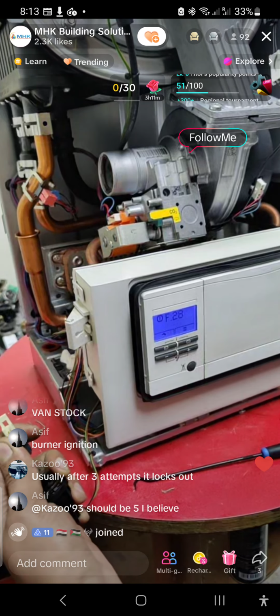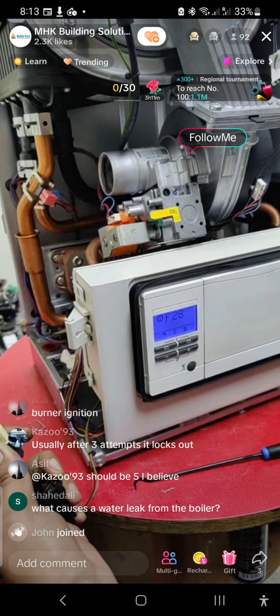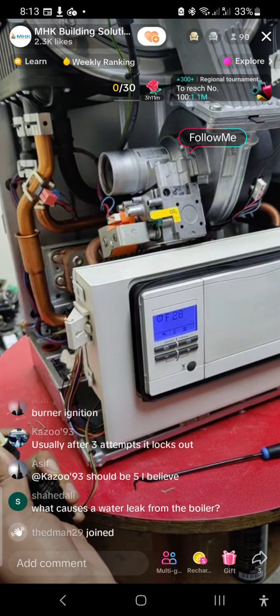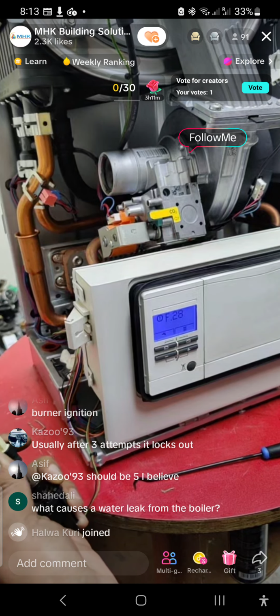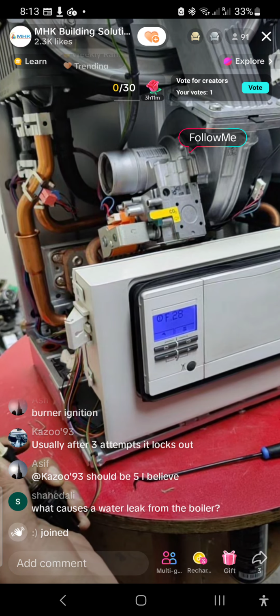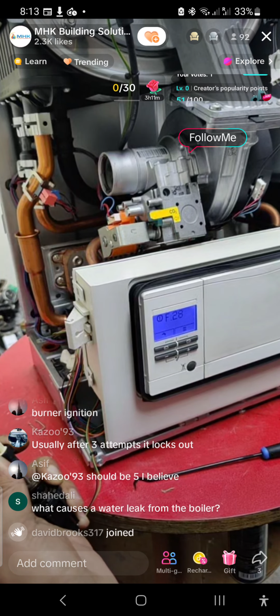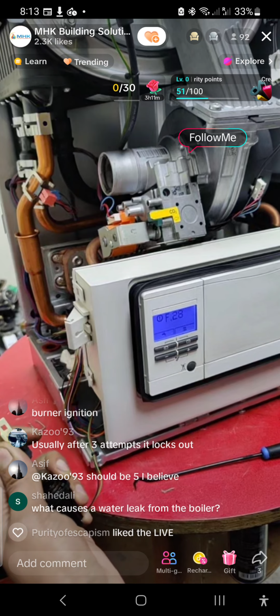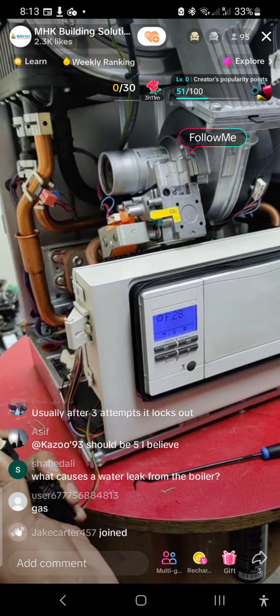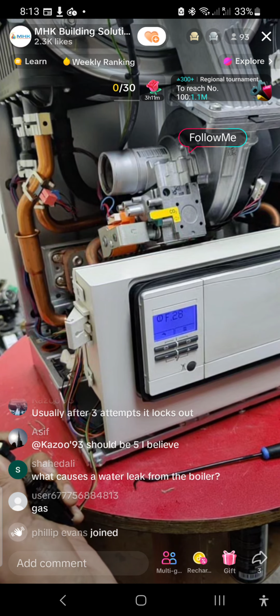Usually after 3 attempts... okay guys, it's moved to an F28 fault now. If we have a look at F28, that should be ignition failure - flame rectification didn't detect anything, as there was no gas. So obviously we have this problem now.